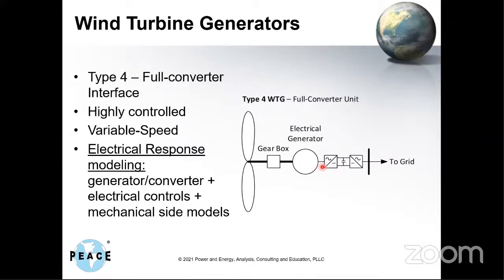And the type 4 is when you put a full powered converter and you basically decouple the generator from the grid. So now everything is controlled by this converter, and it's very tightly controlled, and you can do anything you want with P and Q, basically, within the ratings of the converter, of course. And these machines can be permanent magnet machines, like in the case of vendors like Enercon, or they could be an asynchronous machine like Siemens. And so basically this machine can be any variety of machines.